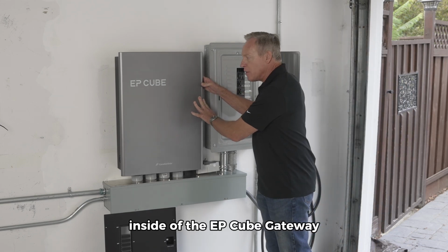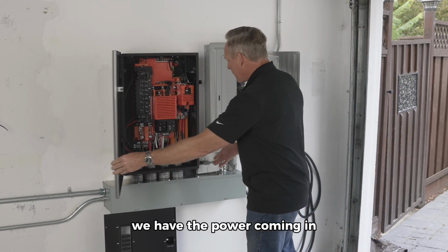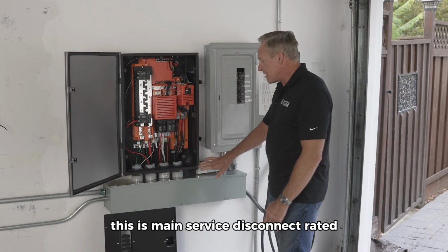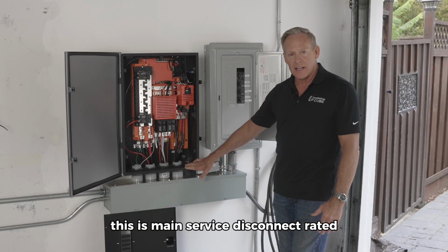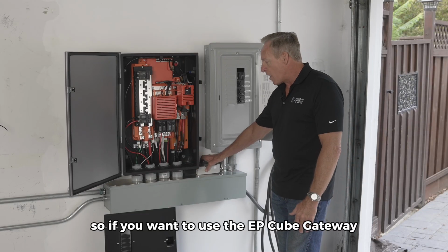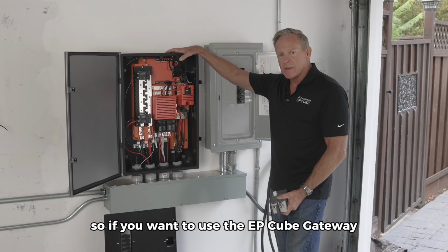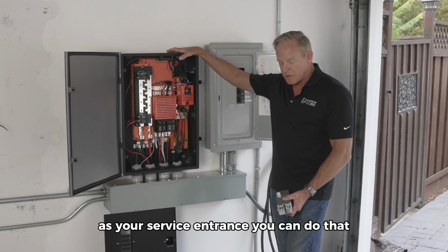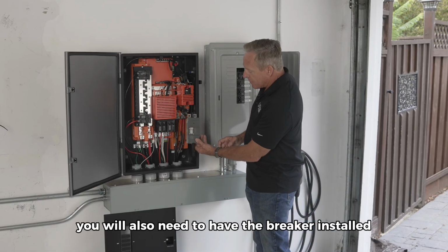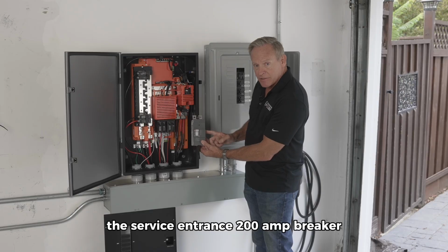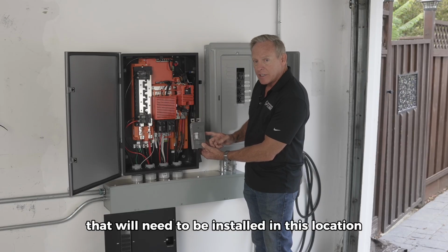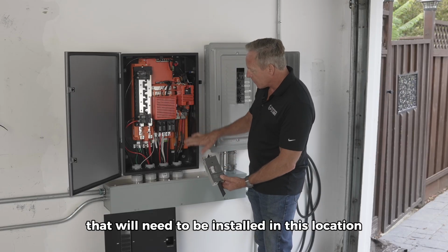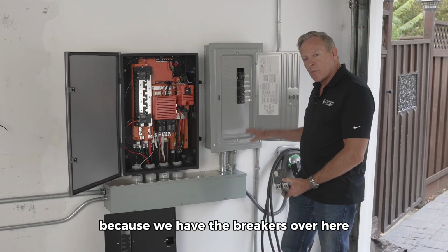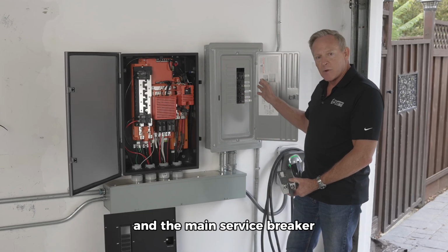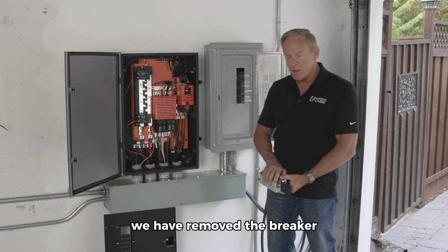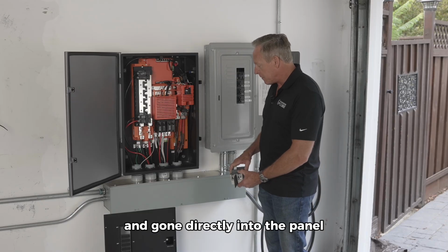Inside the EP-Cube gateway, we have the power coming in. This is main service disconnect rated, so if you want to use the EP-Cube gateway as your service entrance, you can do that. You will also need the service entrance 200 amp breaker installed in this location. Because we have the breakers over here and the main service breaker on the outside of the home, we have removed the breaker and gone directly into the panel.